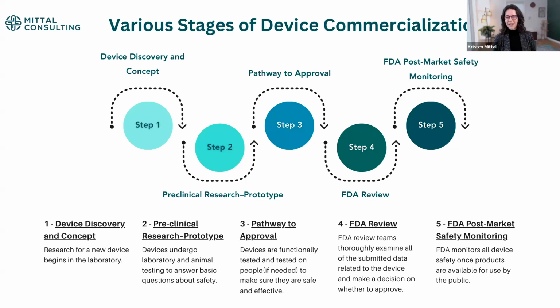You're continuously having to manage that device through post-market safety monitoring. So you still have to do things like MDR reporting. This means tracking complaints, reporting them to the FDA as required, doing corrective actions, removals if necessary, and all of the associated requirements for medical devices once you're on the market. So the monitoring of these devices never stops.